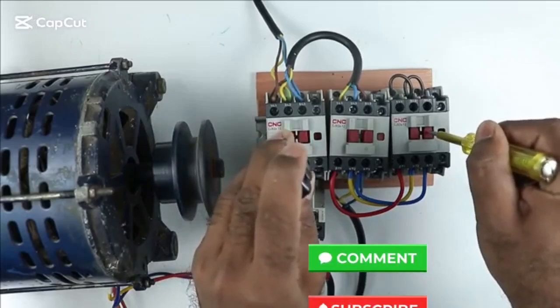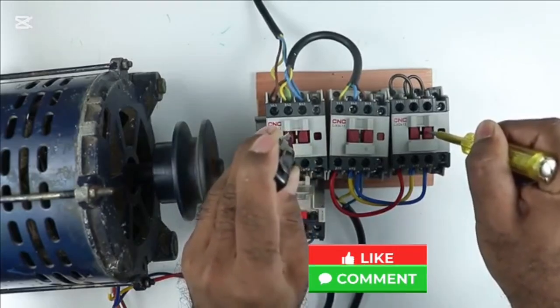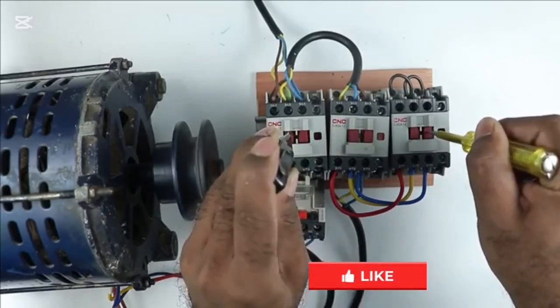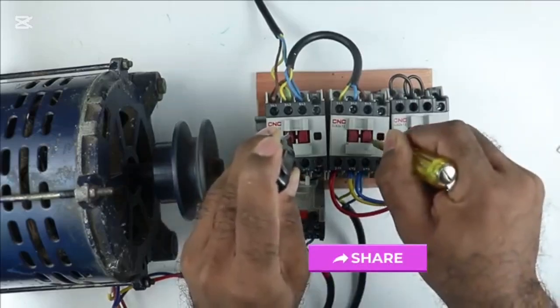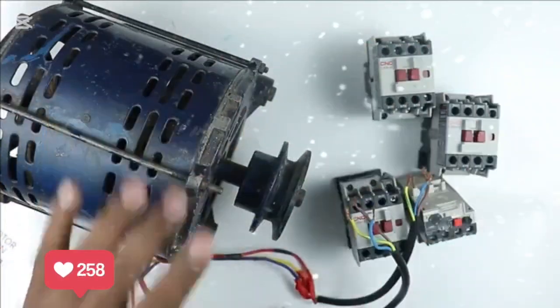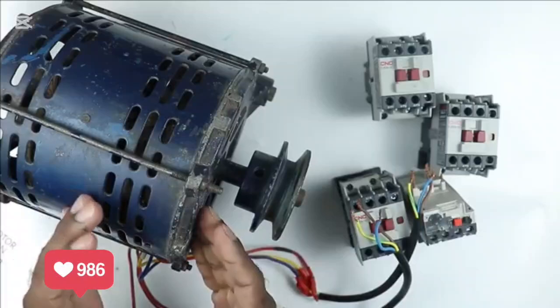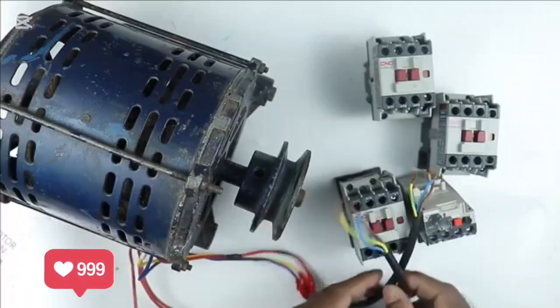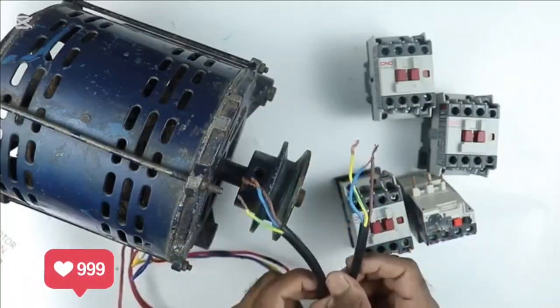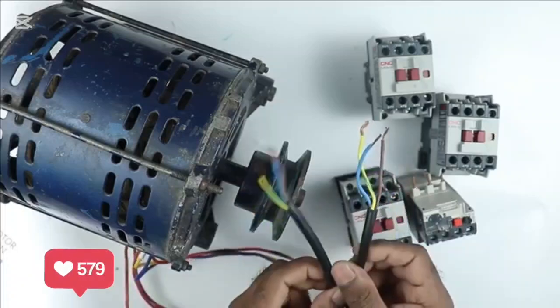See, the motor started running. Now the timer which is connected with the star delta starter will turn off the star contactor and quickly turn on the delta contactor. This 3-phase motor I have now has a total of 6 wires for connection from its winding. By using these 6 wires, I want to make a starter, that is, a star delta starter.